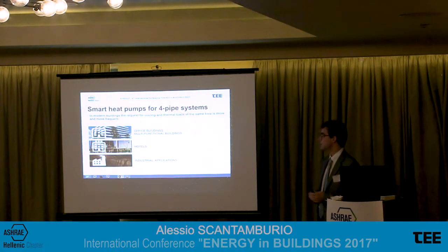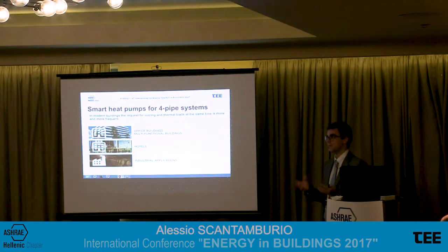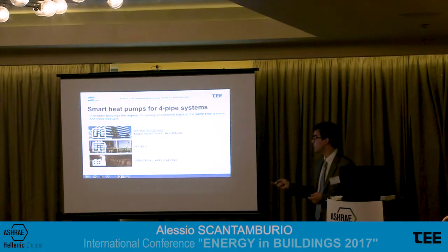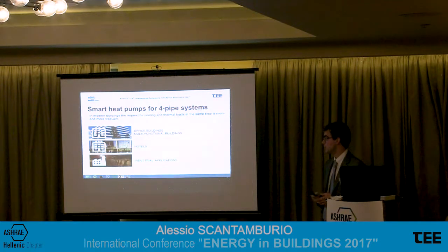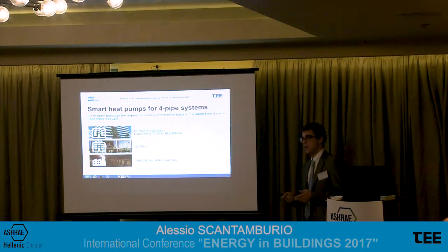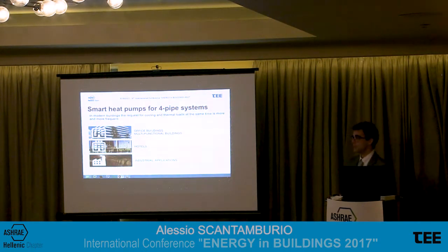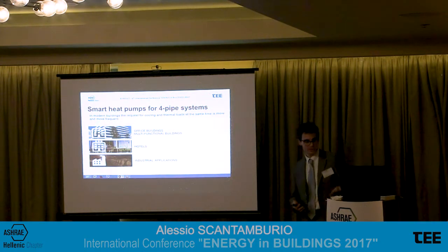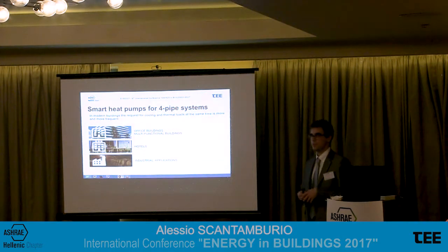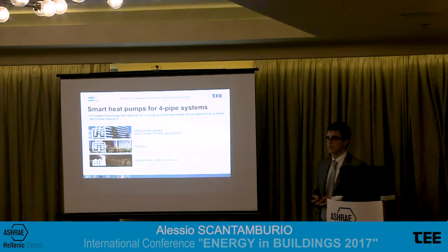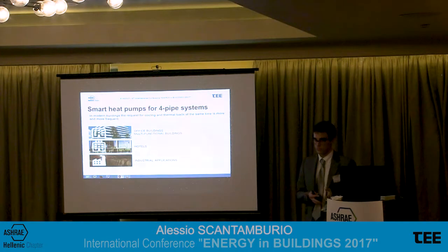In these years it is becoming more and more frequent that the building requires hot water and cold water at the same time. This is due to several reasons. For example, if we consider office buildings or multifunctional buildings, modern architecture has large glazed surfaces, so solar heat gains can be really high also during the cold season. And each of us uses a PC and other machinery which produces heat, so internal heat gains are really huge also in the cold season.